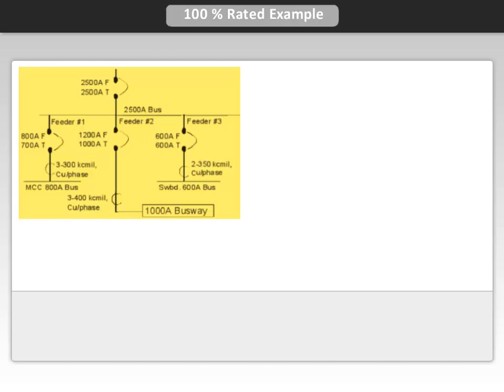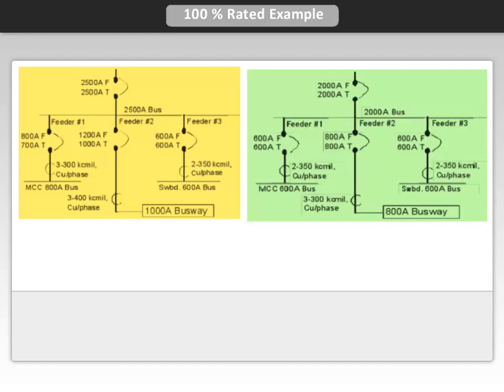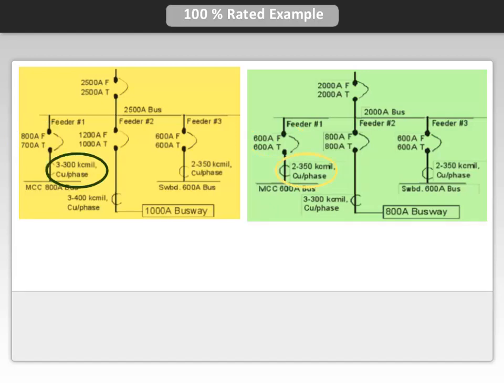These values are displayed in this single line diagram. Now let's see what happens when we use 100% rated breakers by comparing diagrams side by side. Feeder number 1 has a combined load of 600 amps, so we can use a 600 amp 100% continuous rated breaker. By doing so, we can now use a smaller cable size and the MCC bus now only needs to be rated at 600 amps.